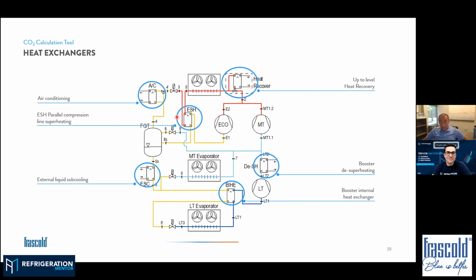We can have superheating for the parallel compressor. We can add external subcooling for increasing the quality of the liquid entering these cabinets. Sometimes this is life-saving for the compressor: the internal heat exchanger on the gas suction line of the low temperature compressors.